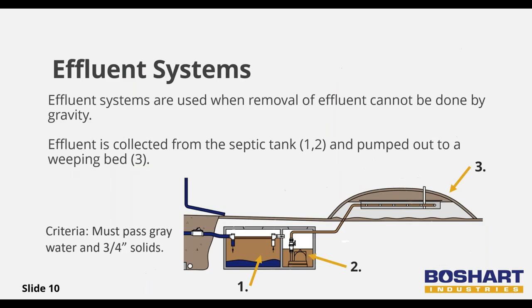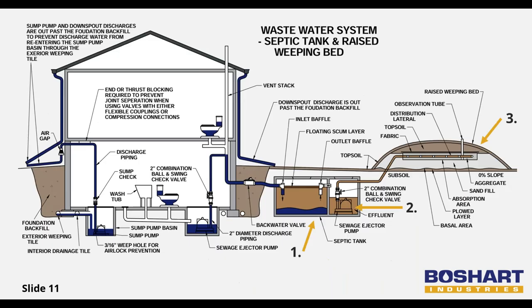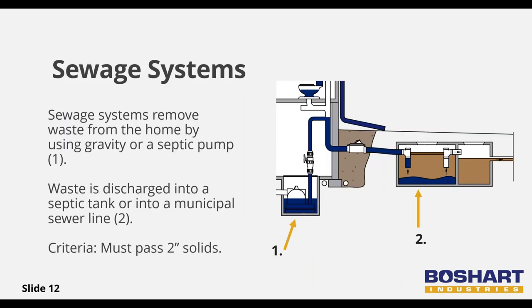Effluent, also referred to as gray water, collects in the septic tank as it separates from solid waste (arrow one). In an effluent system, that gray water then flows and is stored in an effluent tank (number two), where a sewage ejector pump can discharge the waste to a weeping bed or municipal piping for treatment (arrow three). The septic tank may not collect all solids, so the effluent pump discharge piping and check valve must handle three-quarter inch waste or larger.